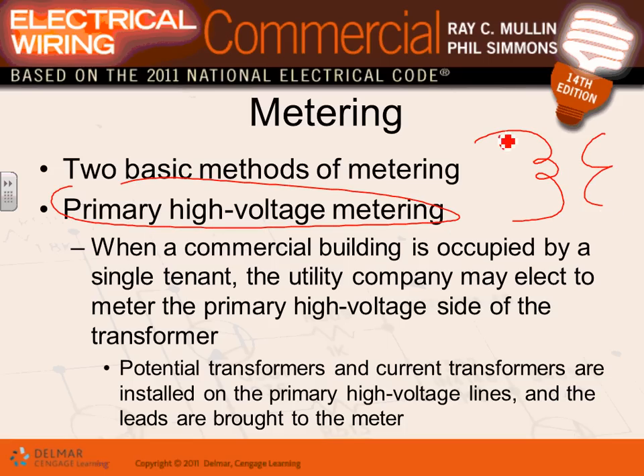What they do is they have a sensor here and they put the meter on the high voltage. That's the high voltage. The low voltage, they put the sensors here and they put the meter here. So Adam, if you put it on this side, it's high voltage metering. If you put it on this side, it's low voltage metering. So most of the metering will happen on the low voltage metering, the utility 480-277, not the 13.8. Very few primary customers have it on the high voltage.